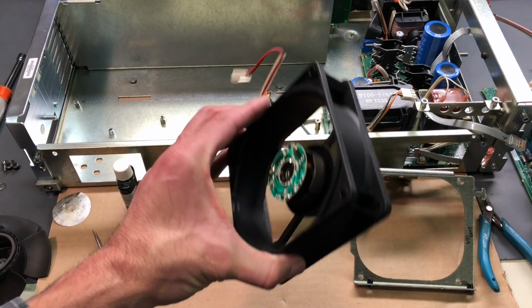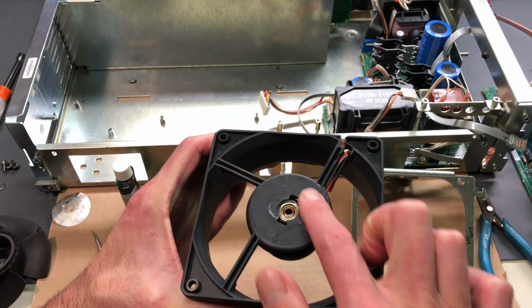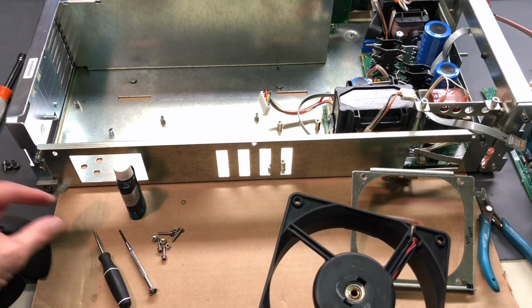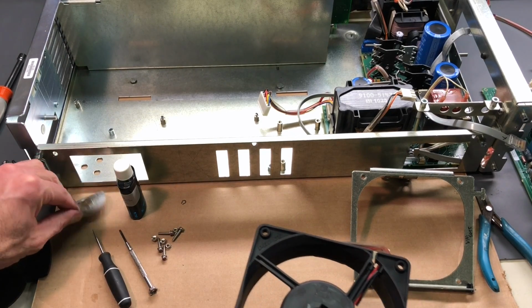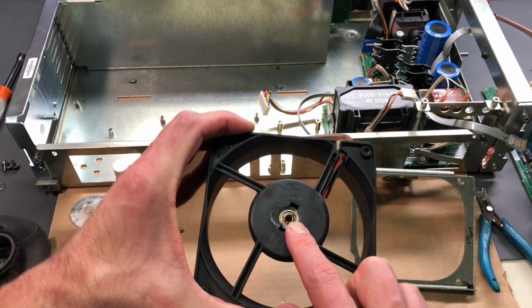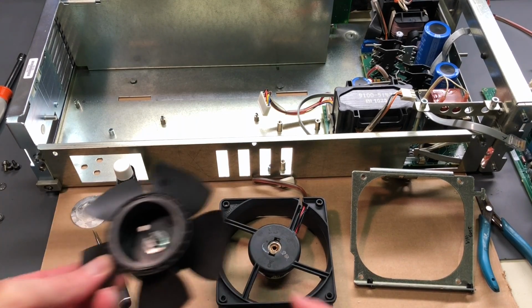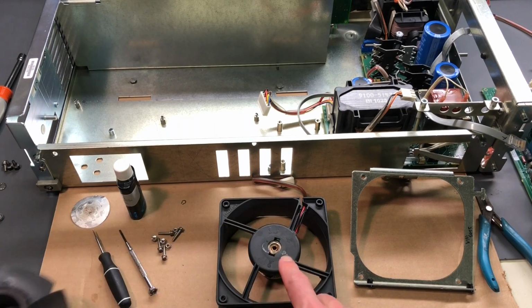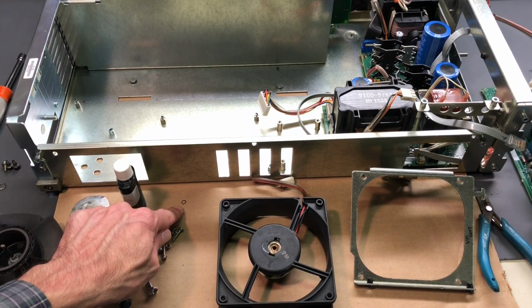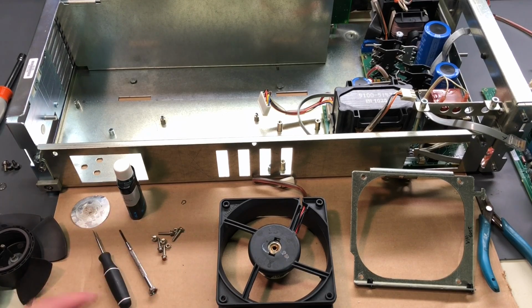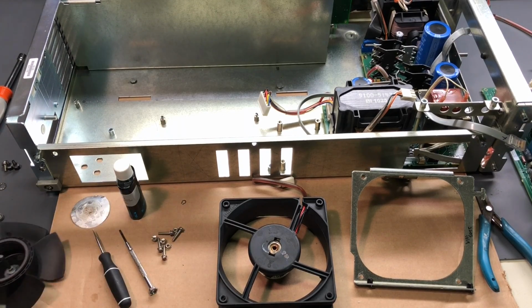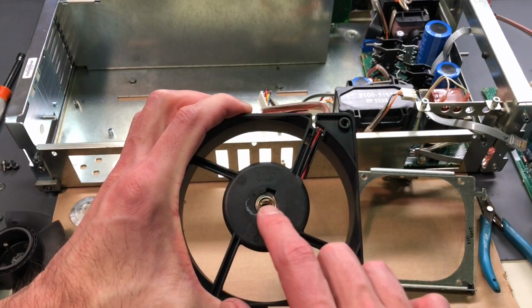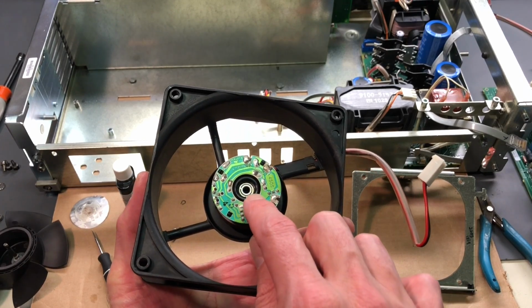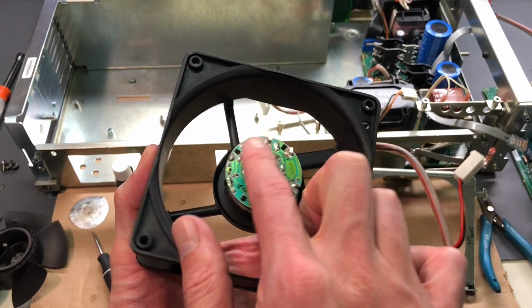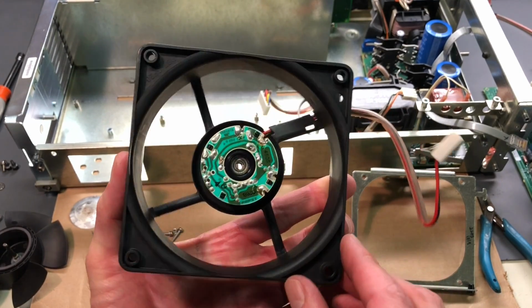So if you're not familiar with how you disassemble one of these motors, on this surface right here, there's a label, which is right here. So you just remove that label, and it gives you access to this bearing. And what you will find is that this shaft right here is poking through the end of that bearing, and there's a little tiny C-clip, very small, you don't want to lose that, but you remove that C-clip from the end of the shaft on this impeller assembly. That drops out, and with that out of the way, you can of course put some oil onto this bearing right here, a drop there, and on this side you can put a drop of oil on that bearing, and the electronics and everything that's on the inside right there, brushless DC motor design.